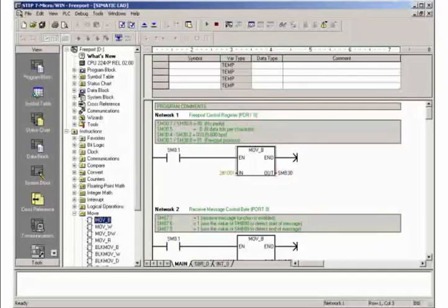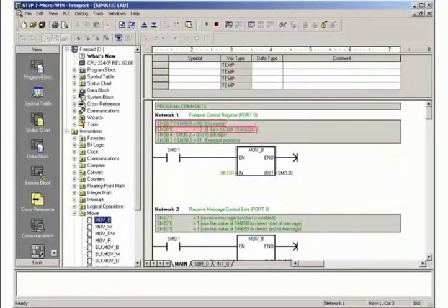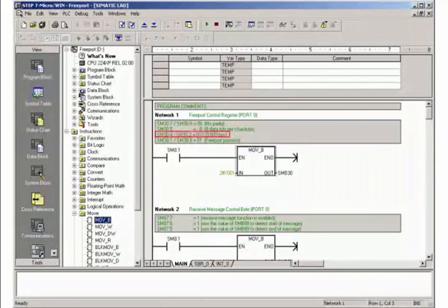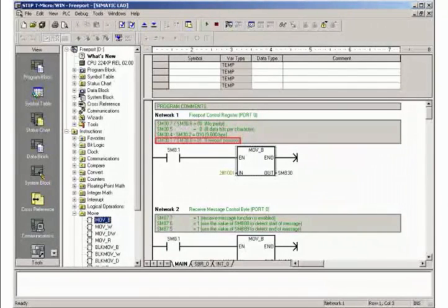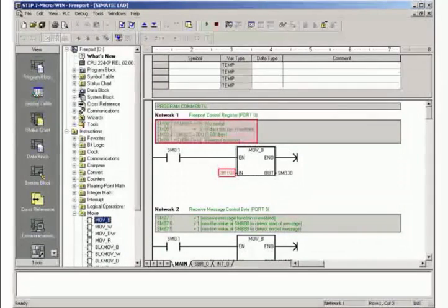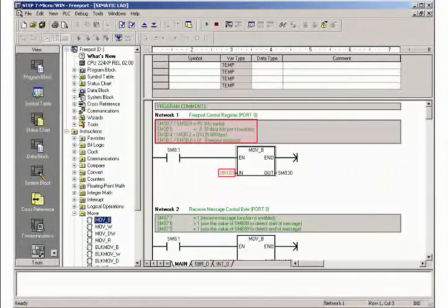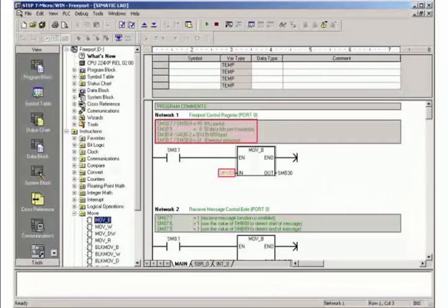Select the following settings: no parity, 8 data bits per character, 9600 bits per second, and activate the free port communication protocol. These settings are later adopted for the RS232 PPI multi-master cable as well as in hyperterminal.